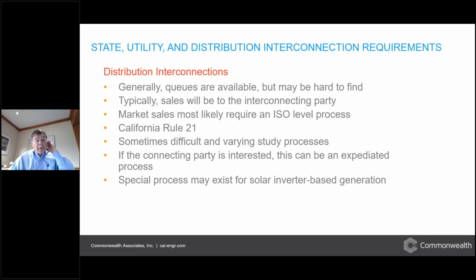I guess I'm ready to move on here, and what we want to talk about is an area that is very, very important, because all that I have said applies, the principle drives through to distribution interconnections, but there are some very important things about them. What I'm really talking about here are interconnections to the grid that's normally at voltages 34.5 kV and below. So you might have an interconnection at 34.5 kV. There are some 25 kV distribution systems, and certainly 13.8 and even lower.